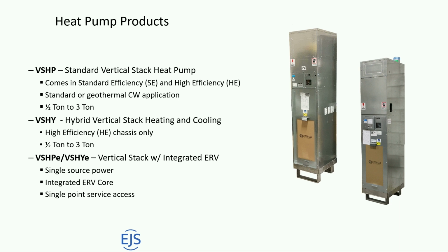So you can get the 105 from a water-to-water heat pump. You can maybe use solar. We're doing a couple projects where we're using solar heat to raise the temperature of that water, and we can get heating at 105. You can also use that coil for a free cooling or heating coil, which a couple projects we're talking about that. And then you have the compressor for backup cooling and heating. Then we have the VSHP-E and VSHY-E, so your regular conventional heat pump and your hybrid with a built-in energy recovery ventilator. So the ERV is going to be, these units typically are installed in the exterior parts of the space, so along the walls, and they're exchanging heat from your bathroom exhaust.